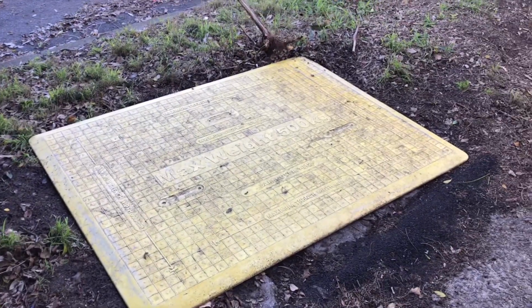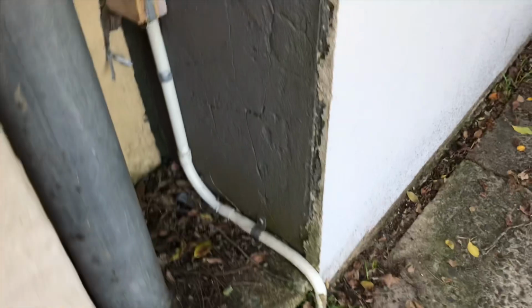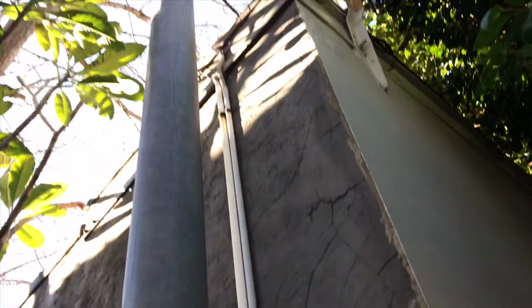There's definitely a lead-in. The pit here, it's a damaged pit, it's an old steel lid and stuff. I'll just pop it up here and have a quick peek under here. But that's the old pit, it's an old manhole actually. To the manhole, but you can see the conduit comes in and there's a box there, all right? And then from there, that conduit goes up there.